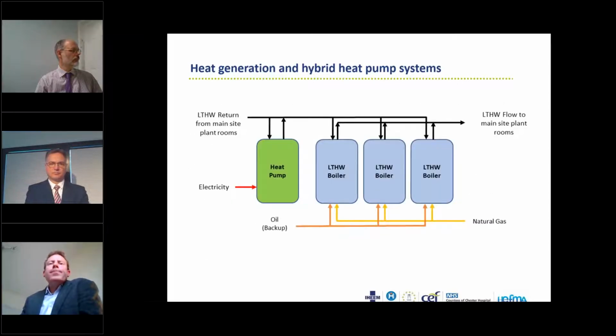So here we can see what we can do. If we've got our low temperature network running effectively, we can put a heat pump in on the return leg back to the boiler house, and look to preheat the returns with the heat pumps before they get to the boilers. So we're starting to build heat pumps into that low carbon technology in our solution.